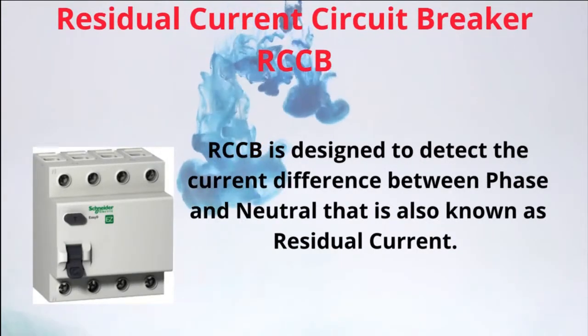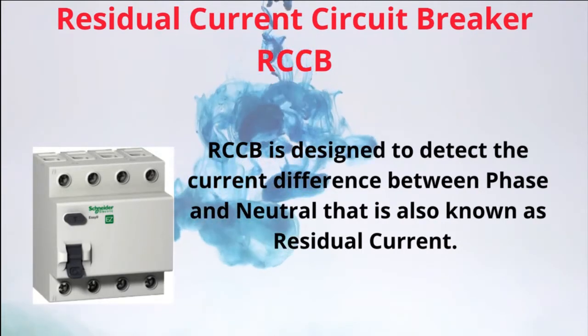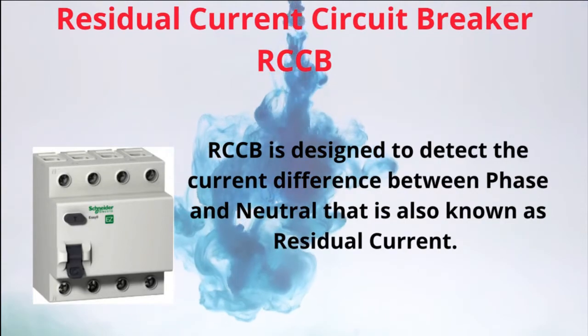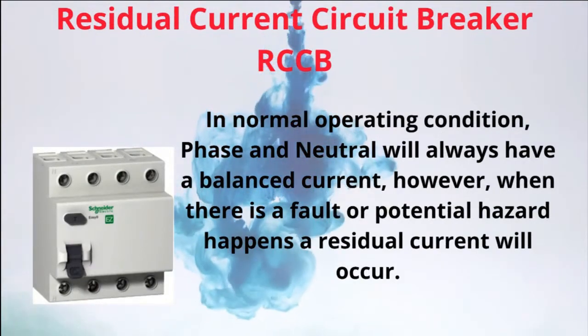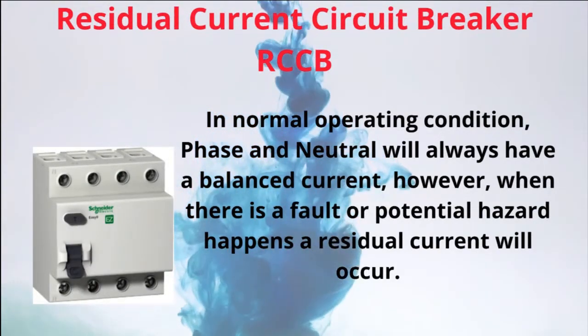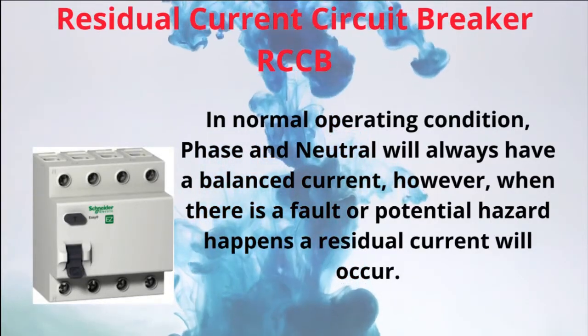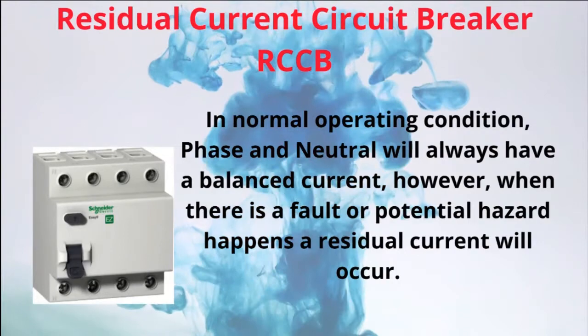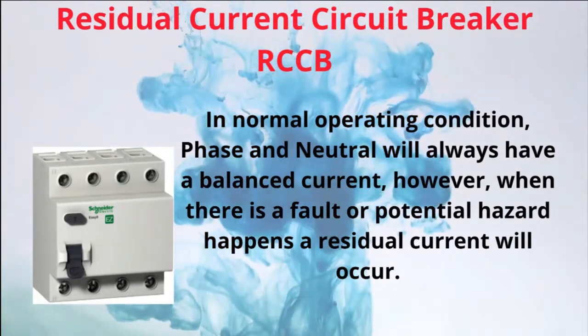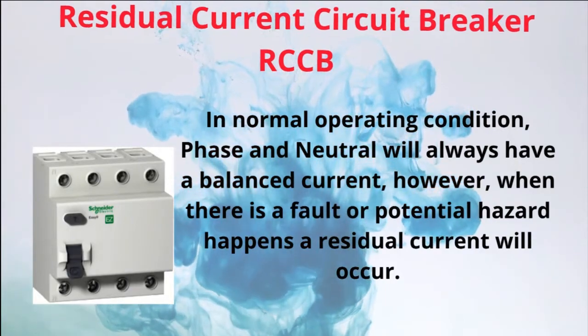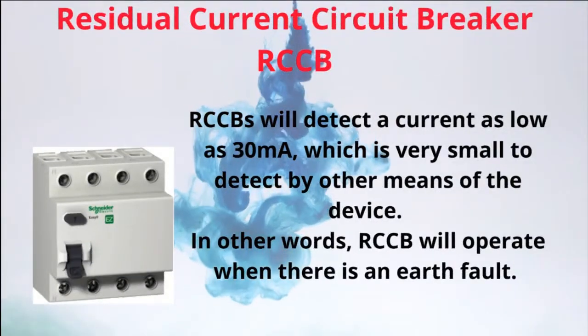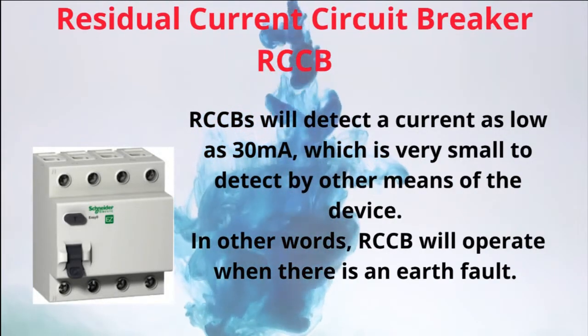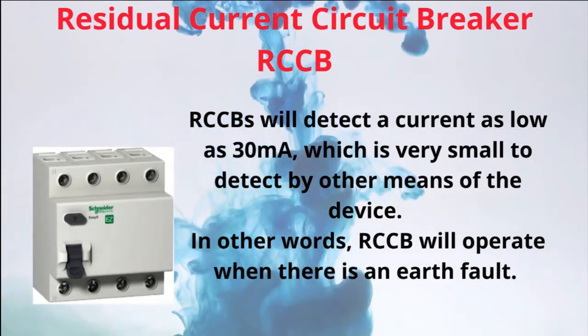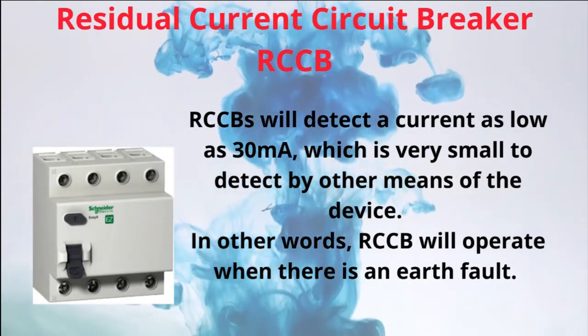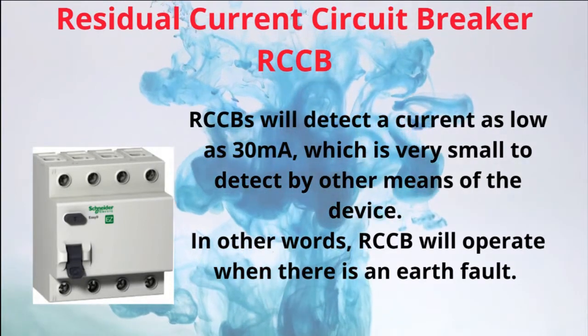RCCB, residual current circuit breaker. RCCB is designed to detect the current difference between phase and neutral, which is also known as residual current. In normal operating conditions, phase and neutral will always have a balanced current. However, when a fault or potential hazard happens, a residual current will occur. RCCBs will detect a current as low as 30 mA, which is very small to detect by other means of the device. In other words, RCCB will operate when there is an earth fault.